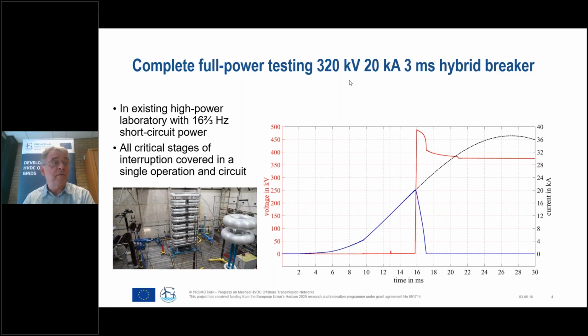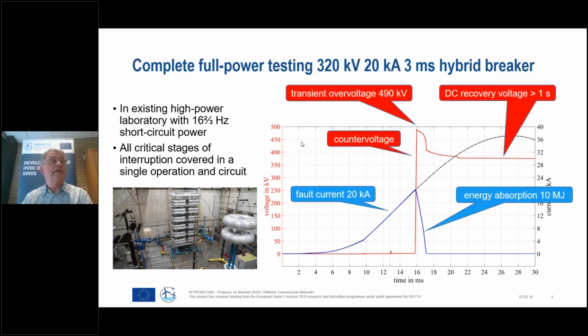To the right side of the screen, you see our most far-reaching test: a full power Hitachi ABB 320 kV, 20 kA breaker. This is the oscillogram of one of the tests, and here some data are provided. The fault current observed to be interrupted is 20 kA against a transient counter voltage of around 500 kV, with an energy absorption of 10 megajoules.